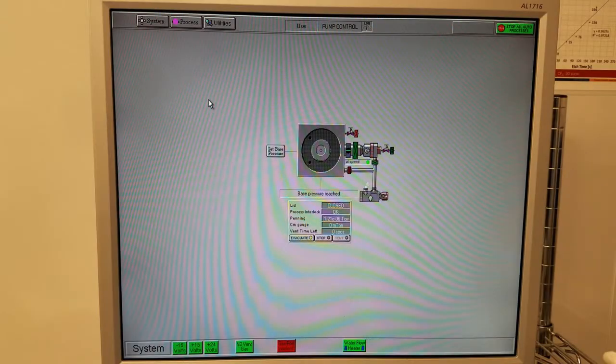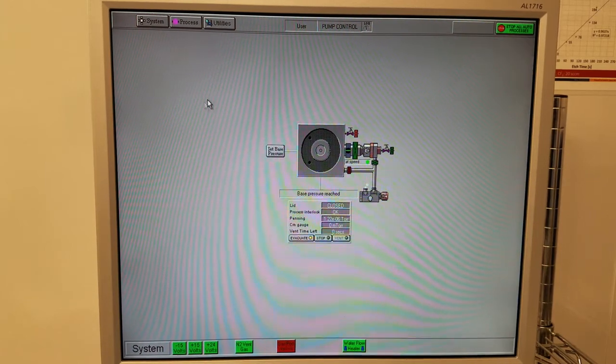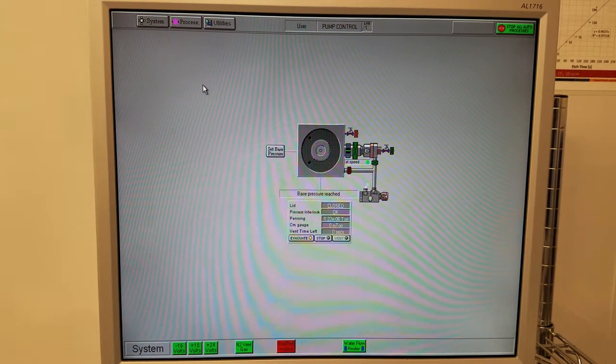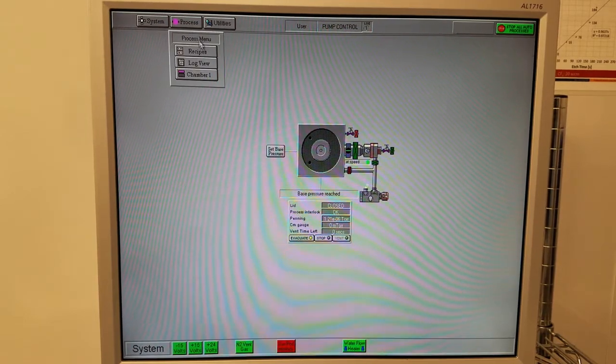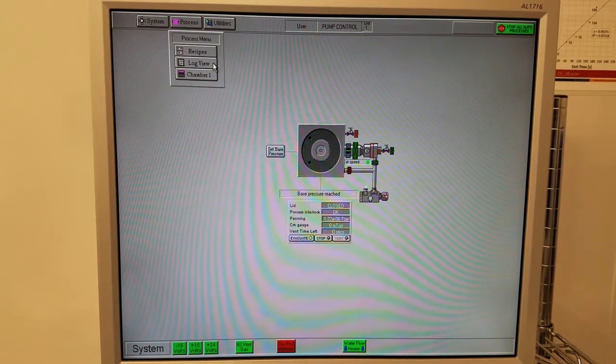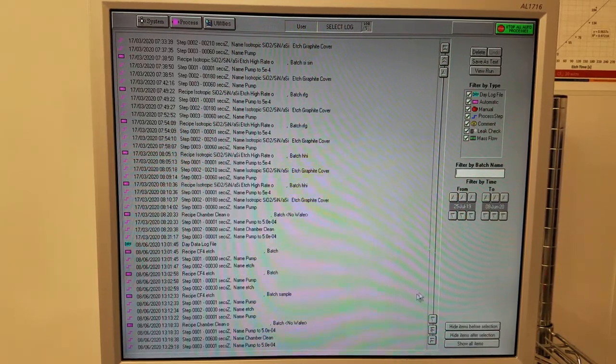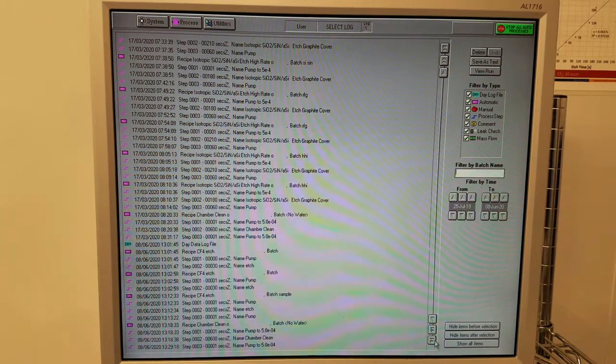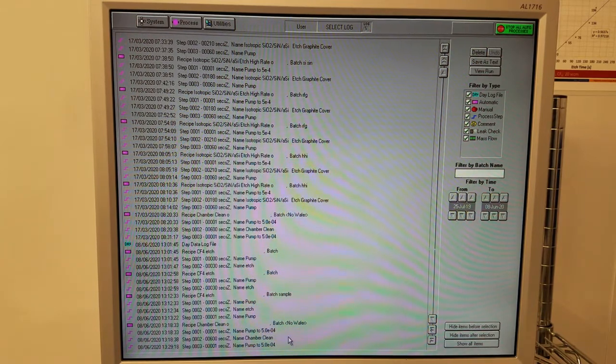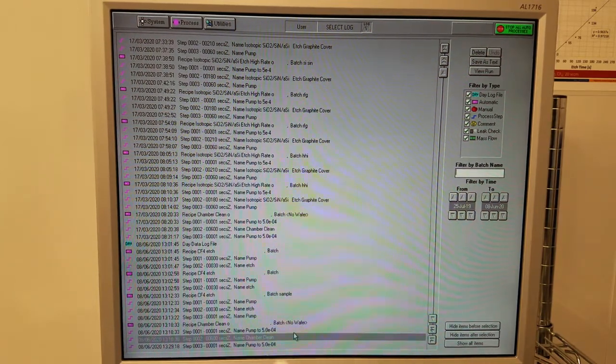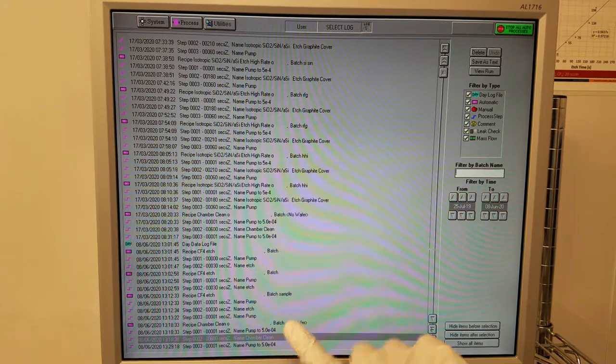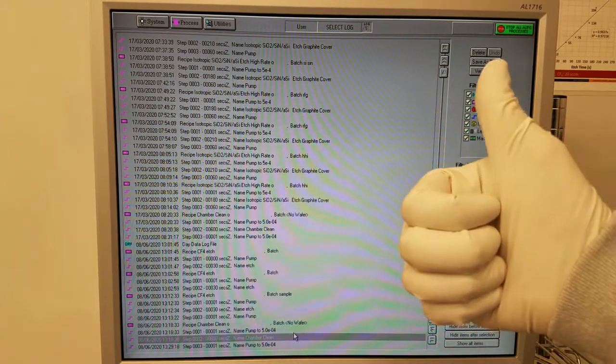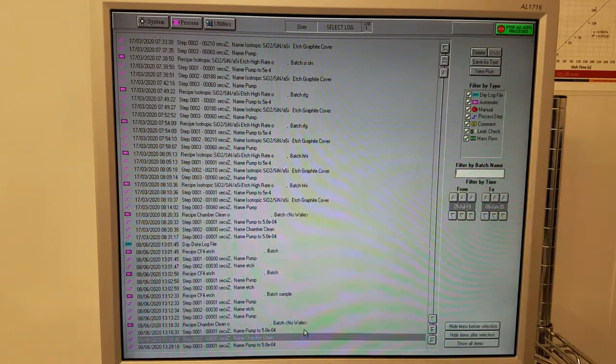The user before you should have run a chamber clean at the end of their run. You should first check to make sure that they did, in fact, do this. Click process, log view, and go all the way to the bottom. The second to last entry should say chamber clean. This time, the previous user ran it. But let's see how to do this if they didn't run the chamber clean.